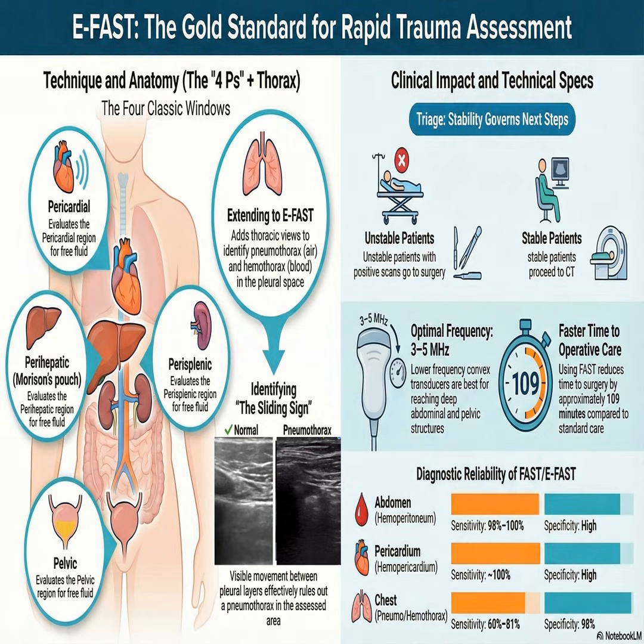So the physical properties of the transducer you select really dictate your diagnostic capabilities. Linear probes use higher frequencies, typically 6 to 13 megahertz. Emitting waves in a straight parallel configuration, yeah. While convex or curved probes use lower frequencies, usually 2 to 5 megahertz, and emit waves in a fan-shaped pattern. And this represents the inescapable physics trade-off between resolution and penetration. It's like a floodlight versus a laser pointer. That's a perfect analogy. Higher frequencies, your laser pointer, provide exquisite axial and lateral resolution.